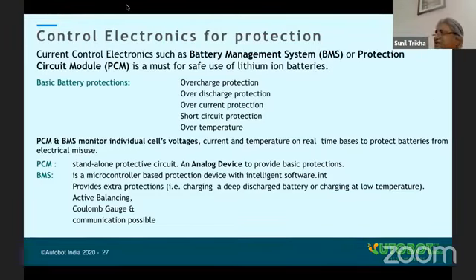There are temperature sensors placed at the most critical places, where the core cell temperature can go maximum. These sensors are designed to monitor the worst condition, and if the temperature exceeds the limit, it cuts off charging or discharging at that stage. So these are the various controls done by BMS or PCM.